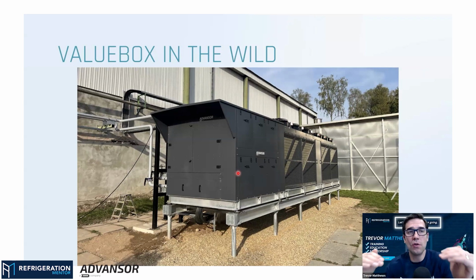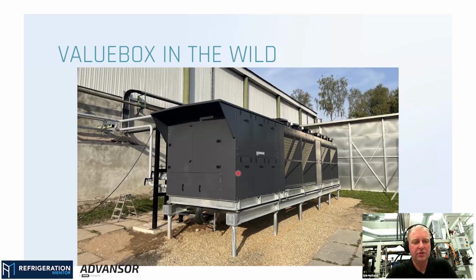So at that time, I'm assuming you're watching the sight glass and the pressure in the receiver and the flash tank as you're charging it, because in the field sometimes you don't always know how much. You would know how much CO2 this system is going to take, but a lot of technicians may not know. So you're watching the pressure and the sight glasses on the flash tank receiver? Yeah, we always monitor the pressures and the levels. As soon as we have a minimum level on the system, we're basically ready to start up. But preferably, the more liquid you can get in the flash gas tank directly, the better, because you have a larger connection and it will go faster.